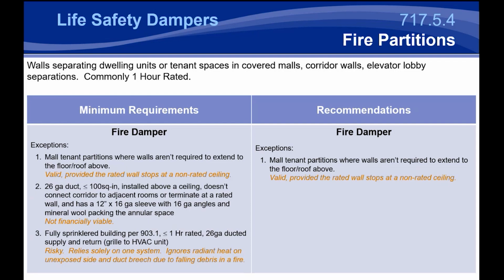And certainly for these multi-tenant penetrations that didn't extend from the floor to the roof above, you could remove the fire damper. It's certainly valid. Pretty much any damper in a non-rated construction will not supply you with the needed level of protection. Typically, the fire is going to find a way around that non-rated construction and get past that damper. So it's really adding cost without any additional protection.